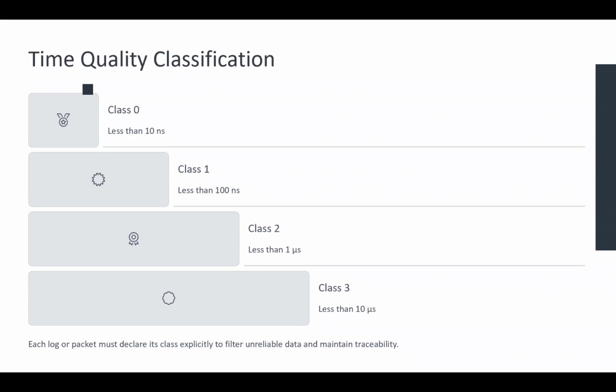Now, we have four primary classes for the time quality. These are not just conceptual groupings. They are quantitative categories that define the hard upper bounds on time uncertainty. So we have class 0, which allows errors up to 10 nanoseconds. This is the highest precision level. Systems operating in this class typically use atomic clocks or high performance GPS. It is required in the telecom timing transport layer and synchrophasor systems, where the angle error must stay under 0.01 degrees. It's also essential in quantum synchronization, radar, or military missile coordination. So this is the highest precision that we could have, class 0.